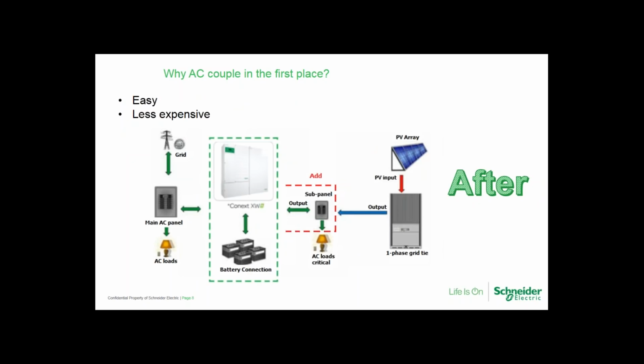So here we can see a system that is AC coupled. And all we've done is we've merely inserted an XW hybrid with the battery, and we've also installed a separate and dedicated sub panel for the critical load. So here we would have your non-critical loads dedicated to the main panel. So the grid goes down, you lose those. And then our sub panel would have our critical loads dedicated to it. And also you would have a breaker that was supplying the PV inverter. So the grid goes down, the inverter switches to battery power, and it fools the grid tie inverter into thinking that the grid is still there, allowing it to come online and continue to produce power.